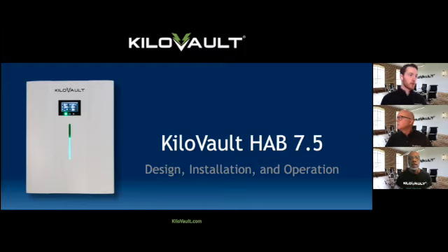Good question from our friend Stefan. In regards to the initial commissioning charge, is it something that you only need to do once, or is it advisable to do it from time to time to recalibrate? I would say you shouldn't have to do it. I wouldn't plan to do it because of the inter-battery communication. Hopefully, once they have been calibrated initially, they'll be able to regulate their voltages and balance each other. If you notice there is an imbalance big enough that the HABs aren't taking care of it for whatever reason, the first step would be to do a calibration charge. But the hope is that you wouldn't have to after the initial one. Now, if you do start to notice the HAB state of charge, which is a calculated value, starts to drift.